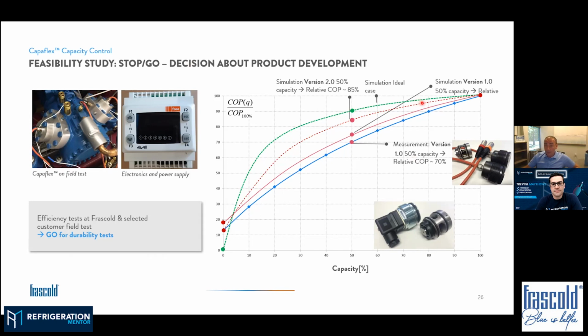From our simulation, the red curve was what we were theoretically capable to reach. Fortunately, the tests were not super far from this value. We saw that we were capable to reach 83% of the COP at 50% of the capacity. And this is what this system is capable to do with two heads or one head.